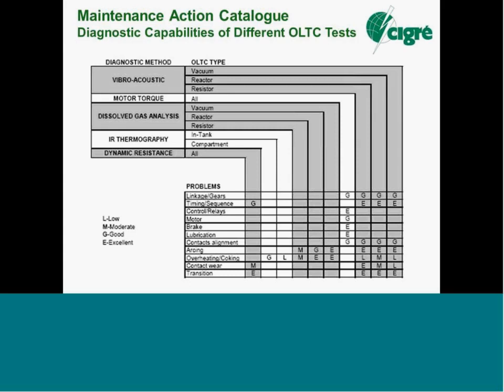So for us, we'd focus more on the resistor OLTC types, and see that for vibroacoustic, let's take that as an example of a diagnostic method, the signature of the ultrasonic microphones, pretty sure, used to detect the vibroacoustic signal from the body of the tap changer. If we have problems with linkage and gears, we have good sensitivity to that problem with vibroacoustics. It's also good for timing and sequence issues, for contact wear and transition resistor problems. Transition in the tap change itself, when the diverter operates. So, useful charts, useful diagrams, all in this brochure.